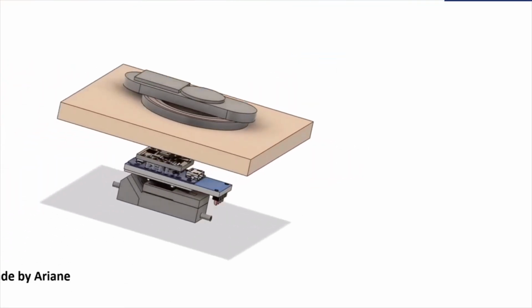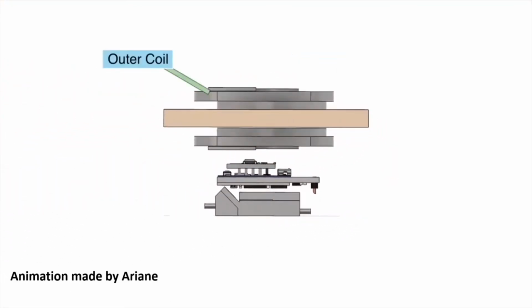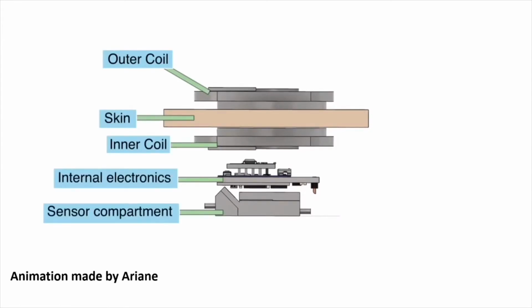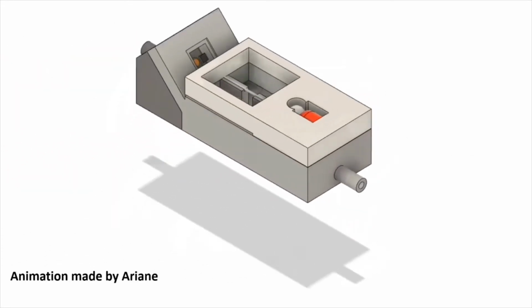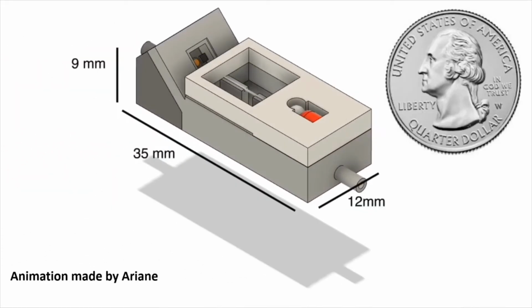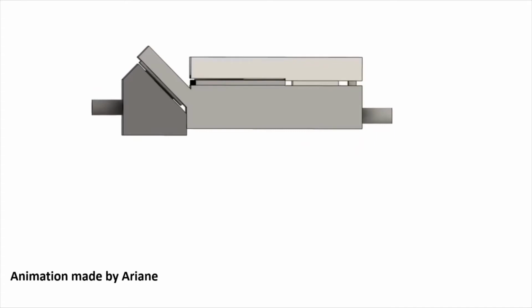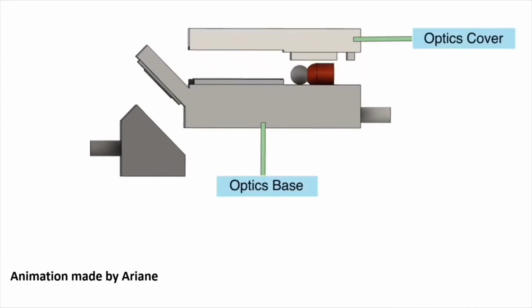Here you can see all of the parts aligned as they would be in the body. On the outside of the body is the outer coil, and inside of the body is the internal coil, the internal electronics, and the sensor compartment. This is the sensor compartment which holds the optical system, flow sensor, and photodiode. It consists of 3 parts: the optics base, optics cover, and sensor holder.